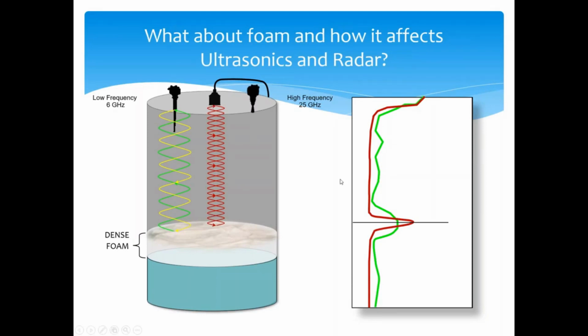Ultrasonic. We actually get a very nice clean signal reflection off of ultrasonic, again coming off the top of that foam layer. And then medium frequency radar, also good clean signal return, and there would be no issues here. So when we're dealing with dense, thick foam, we're going to see that change in dielectric or density off the top of the foam layer, and it shouldn't cause us any real issues.